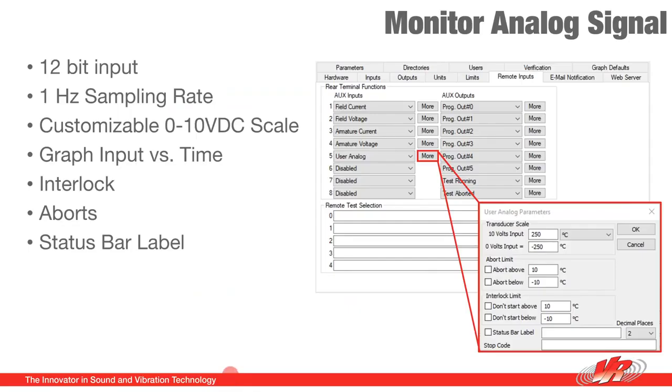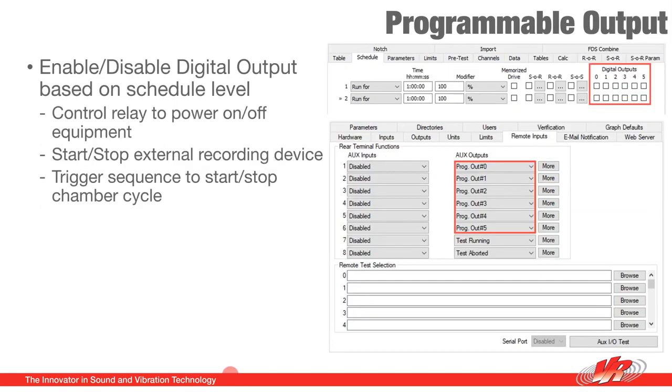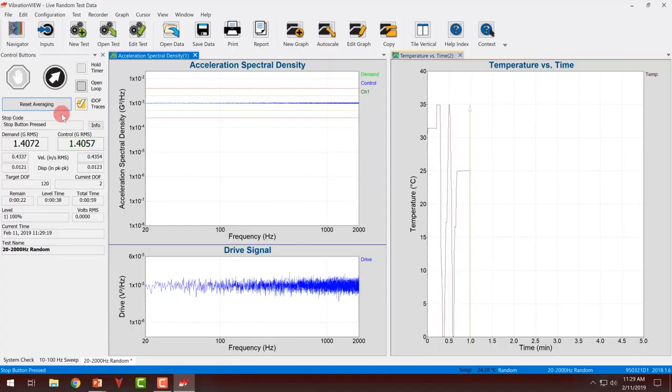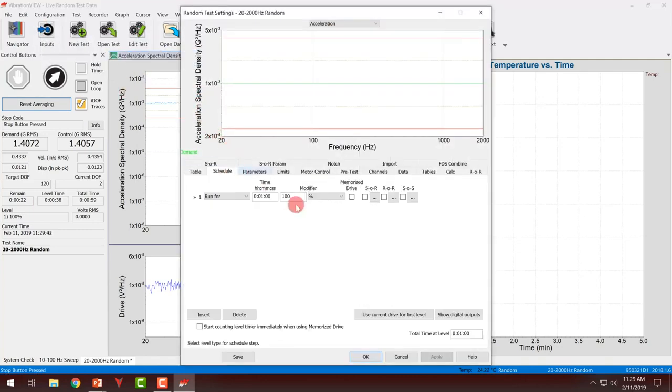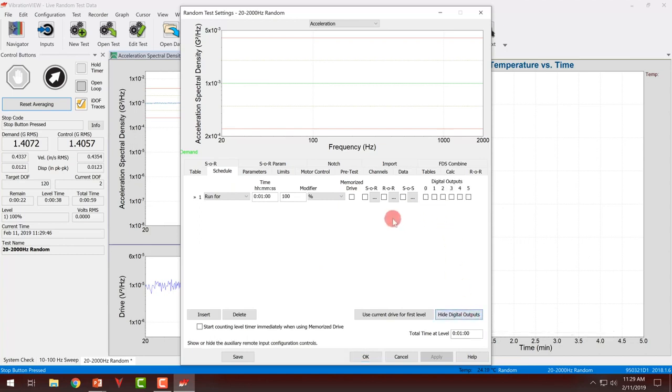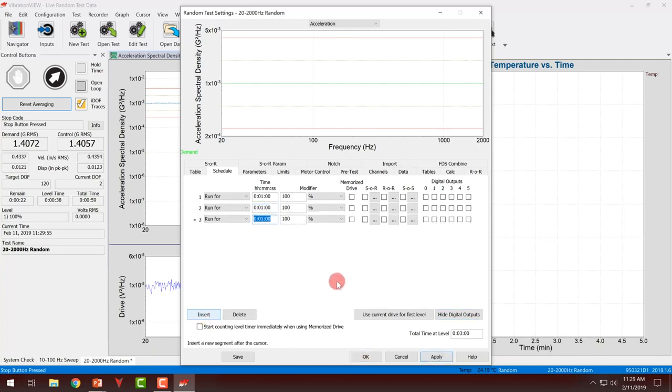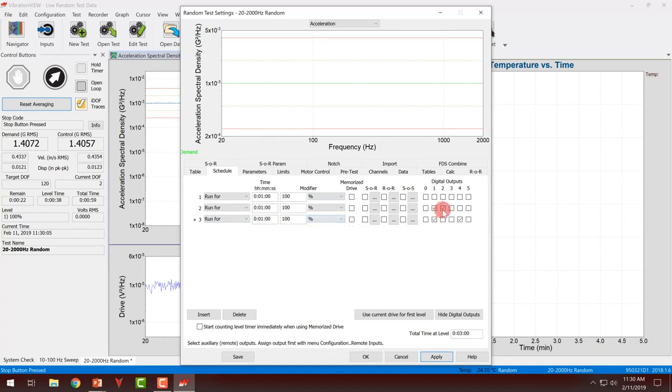Next is the programmable outputs. These are digital outputs that are enabled based on test schedule level. This could be used to trigger some external device, start and stop a recorder, could be used to start and stop a motor, or close a relay while a test is running, or in the middle of a sequence. To do this, I have to first edit my test. On the schedule tab, if I click show digital outputs, for each schedule level, I can have different digital outputs enabled or disabled. As I move through the different levels of my test, these can change. All this is doing is, once this test level starts, those two particular outputs are going to be enabled.